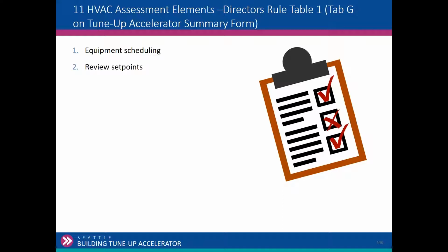Set points. And these are set points based on generally accepted principles. If the discharge air temperature set point was 50 degrees, I go, wait a minute here. The generally accepted set point for discharge air in a central station air handler with zone terminals is 55. Why is it set at 50? That would be a kind of a red flag. If there are reset schedules for chilled water, hot water, discharge air, are there set points for that?